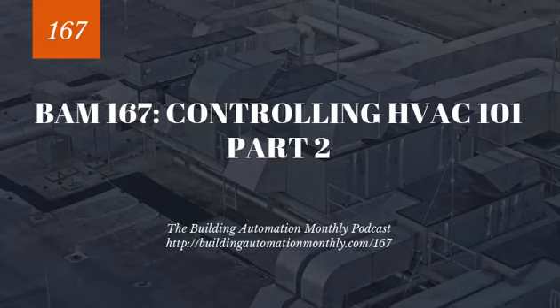Now, when we talk about 100% outdoor air units, why do we use these? Well, there are three main reasons. One is to avoid the reuse of contaminated air. So we don't want to have this mass of contaminated air if we're serving an operating room or if we're serving a clean room.